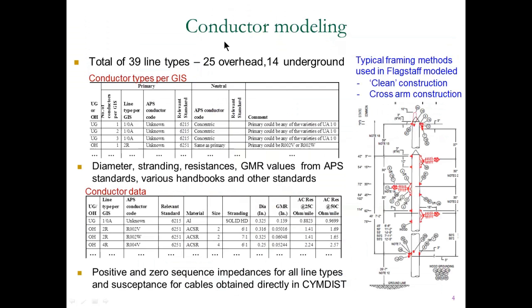Briefly, the equipment modeling, conductor modeling in this slide. There were a total of 39 line types in the primary of the feeder, some overhead, some underground. In addition, there were several secondary line types as well, and they have been modeled as the corresponding triplex conductor types in OpenDSS. For each of these line types, the corresponding models, including the diameter, number of strands, resistance, GMR, and so on, were obtained from various standards and handbooks, and they were used to create the library of the various line conductor types. The level of detail included looking at the specific framing methods used in this feeder, clean versus cross-arm construction, and that was also included in the library of the conductor.